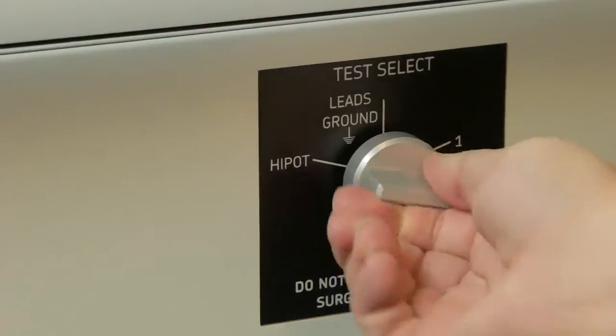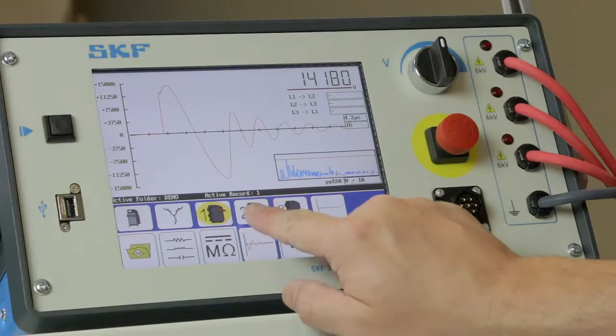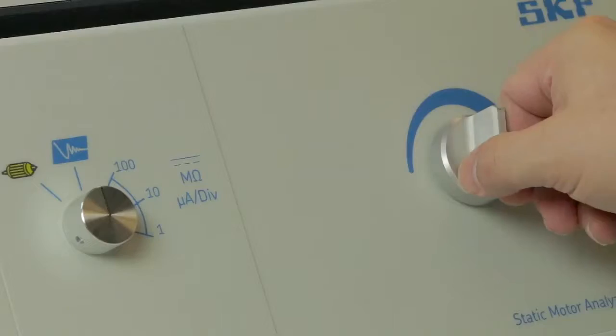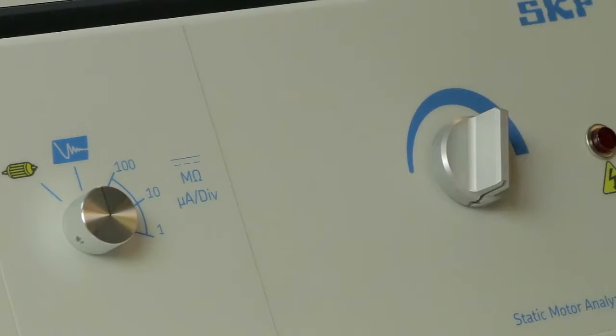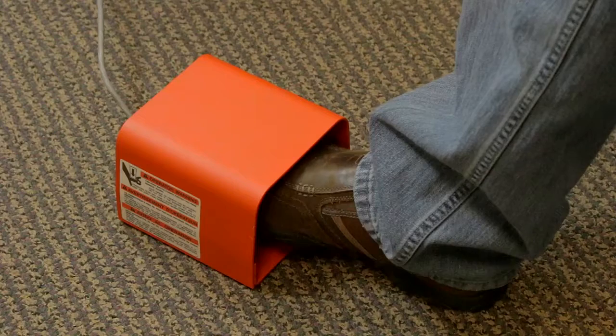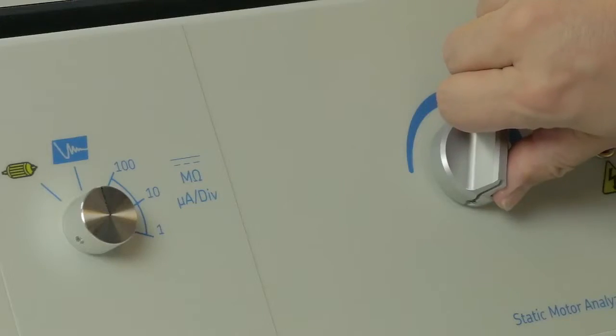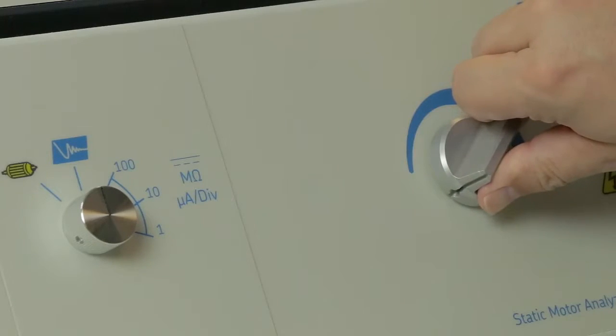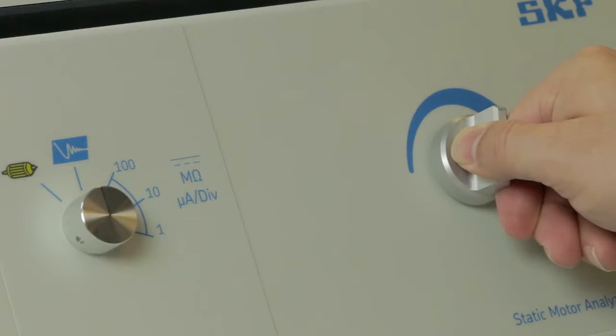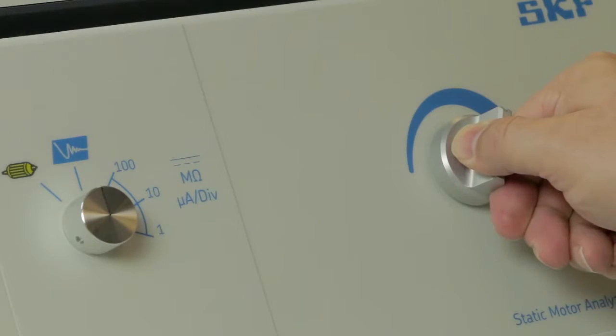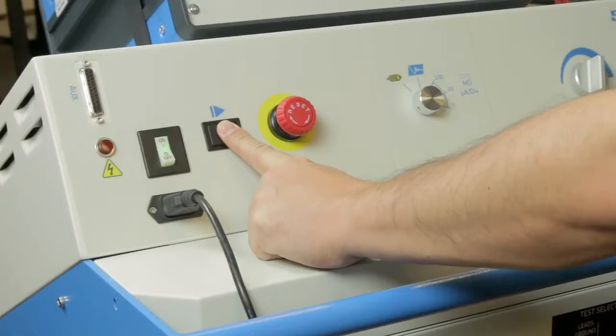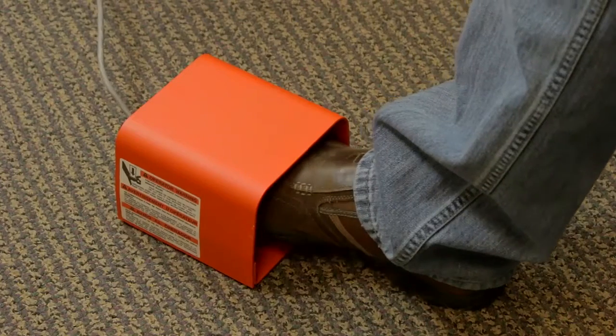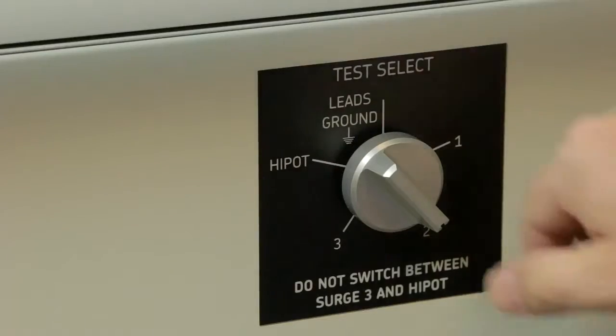Select lead 2 on the power pack and press 2 on the DX. Turn the voltage control knob to 0. Press and hold the push-to-test button or the foot switch. Slowly increase the voltage to the desired test value as before. Release the push-to-test button or foot switch. Repeat the procedure for lead 3.